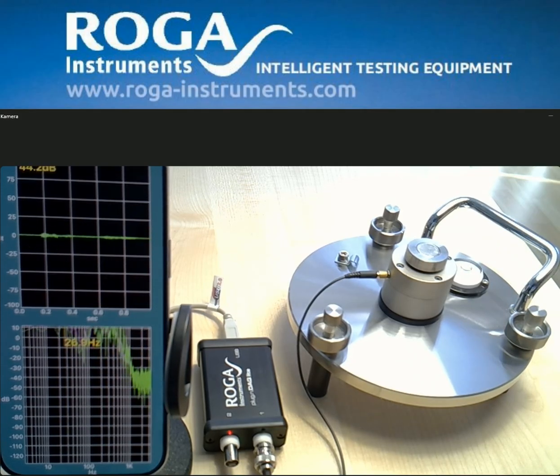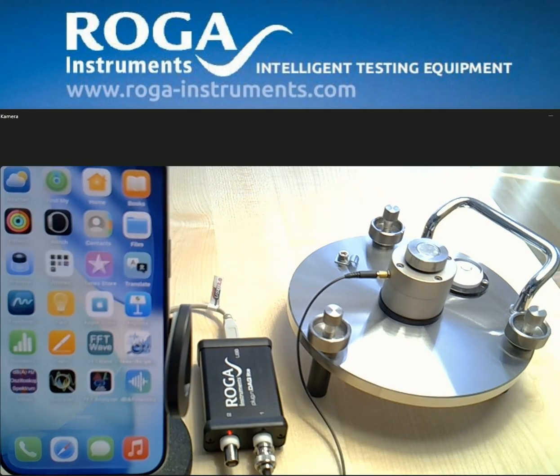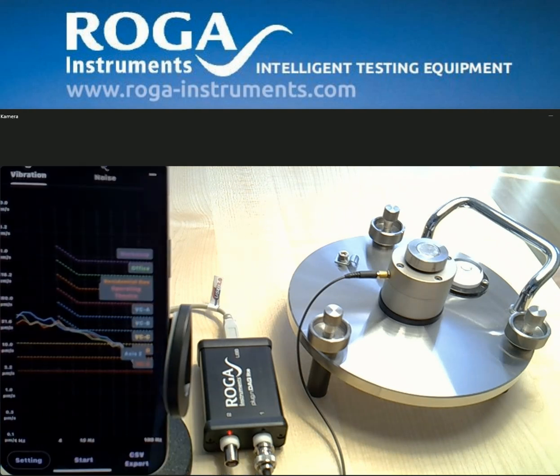So this is now one point, and now I leave this software and go to this software for vibration criteria. This is kind of a rating tool for engineers to determine, before they install, for example, a big microscope into the building with high magnification and so on, or an MRT.